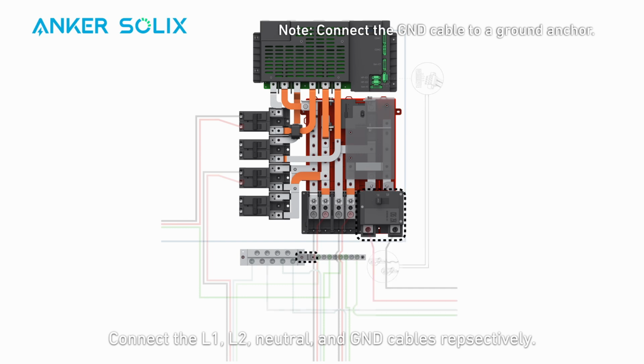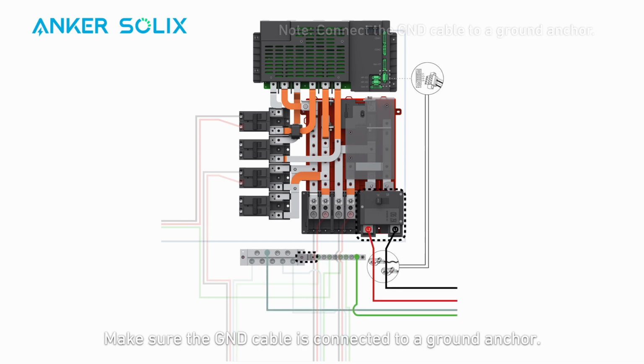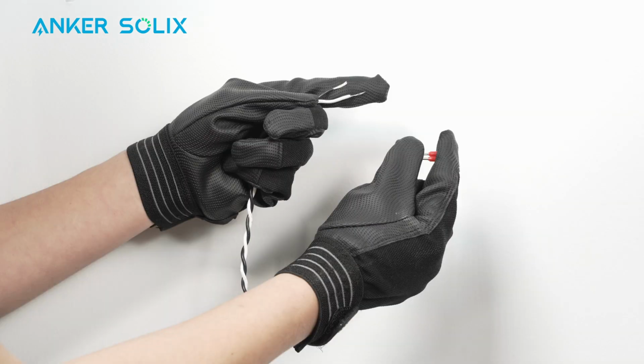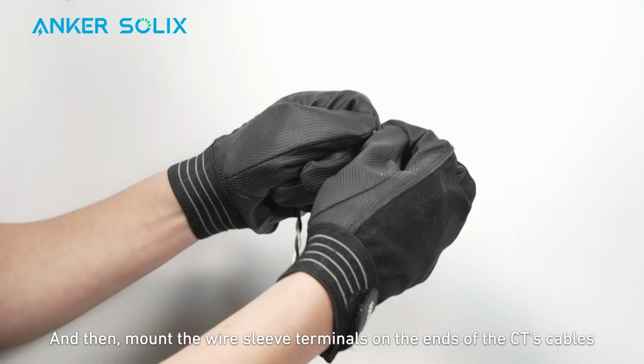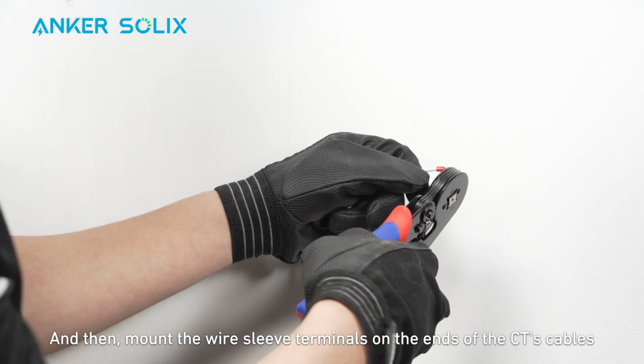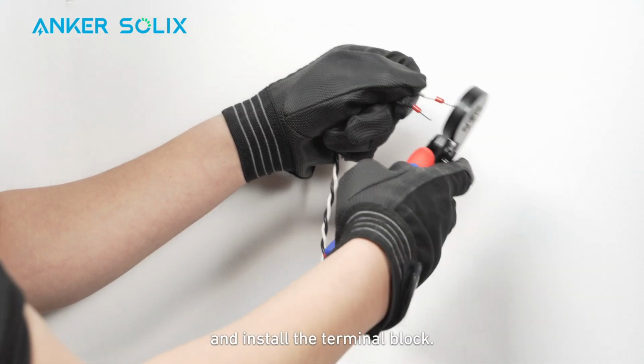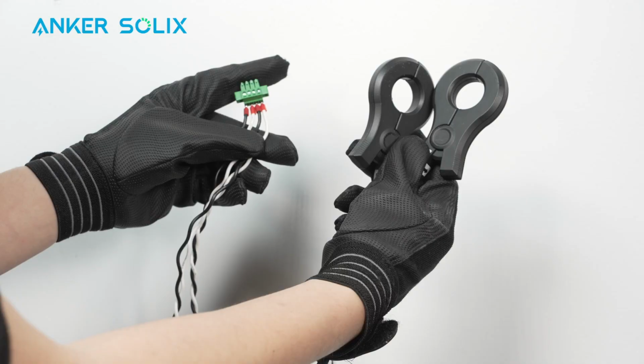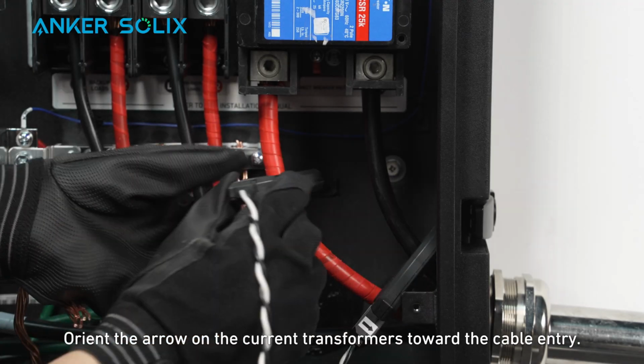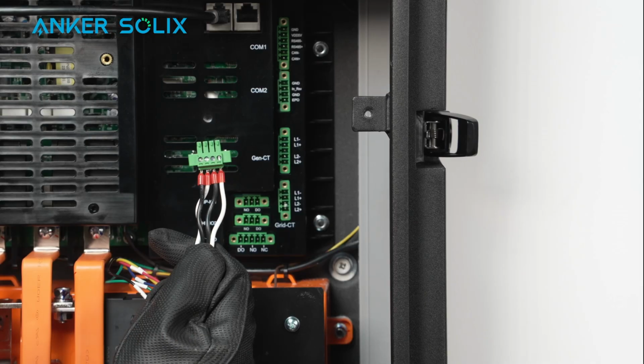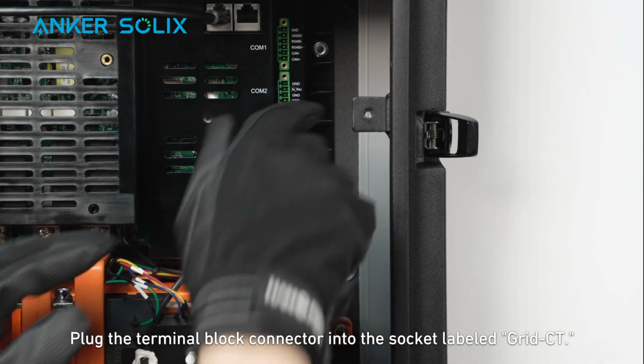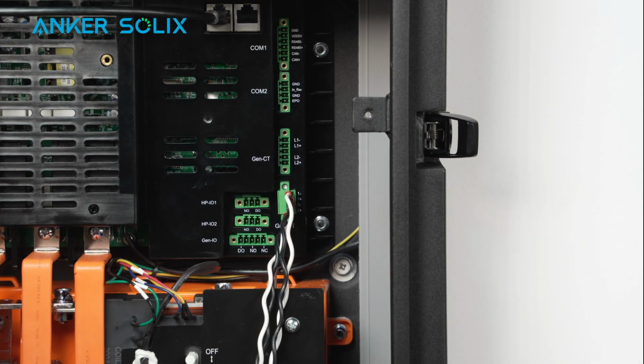Connect the L1, L2, neutral, and ground cables respectively. Make sure the ground cable is connected to a ground anchor. And then, mount the wire sleeve terminals on the ends of the CT's cables and install the terminal block. Orient the arrow on the current transformers toward the cable entry. Plug the terminal block connector into the socket labeled Grid CT.